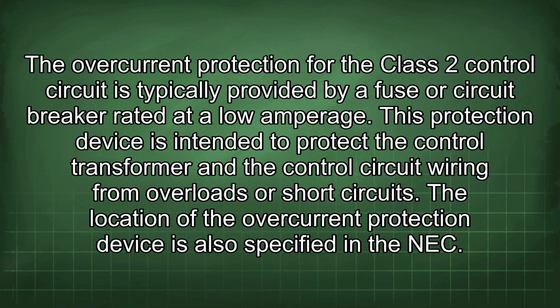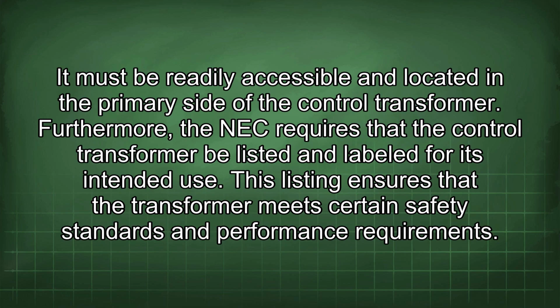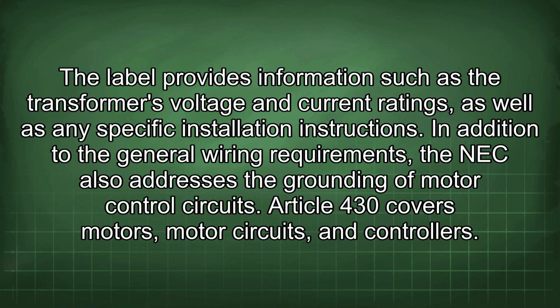The overcurrent protection for the Class 2 control circuit is typically provided by a fuse or circuit breaker rated at a low amperage. This protection device is intended to protect the control transformer and the control circuit wiring from overloads or short circuits. The location of the overcurrent protection device is also specified in the NEC. It must be readily accessible and located on the primary side of the control transformer. Furthermore, the NEC requires that the control transformer be listed and labeled for its intended use. This listing ensures that the transformer meets certain safety standards and performance requirements. The label provides information such as the transformer's voltage and current ratings, as well as any specific installation instructions.